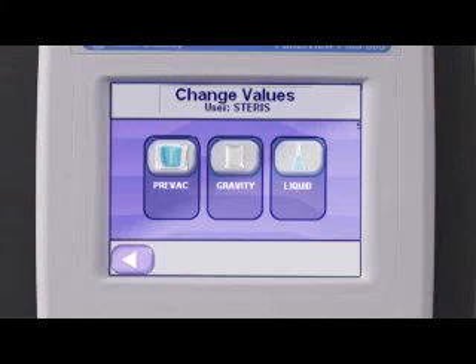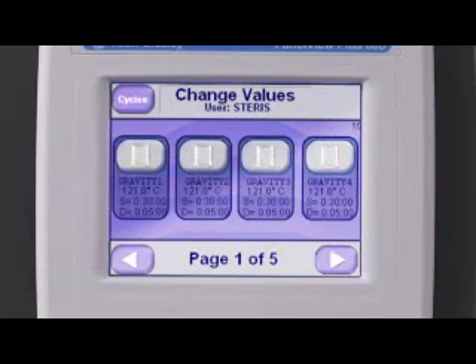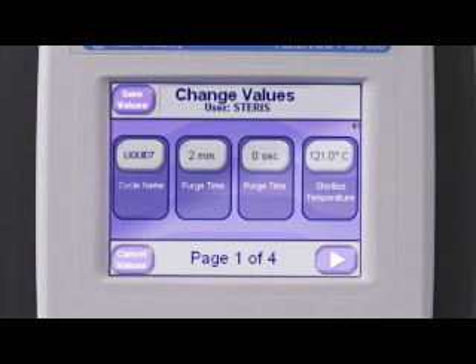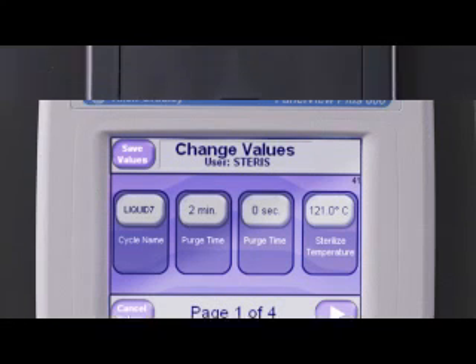Depending on the type of model purchased, the AMSCO Lab Series sterilizer can perform gravity, liquid, pre-vacuum, and isothermal cycles. There are 20 programmable cycles available, allowing the operator to set up cycles for regular loads. Cycles can be user-defined and named according to user, cycle, or whatever is best for the application.